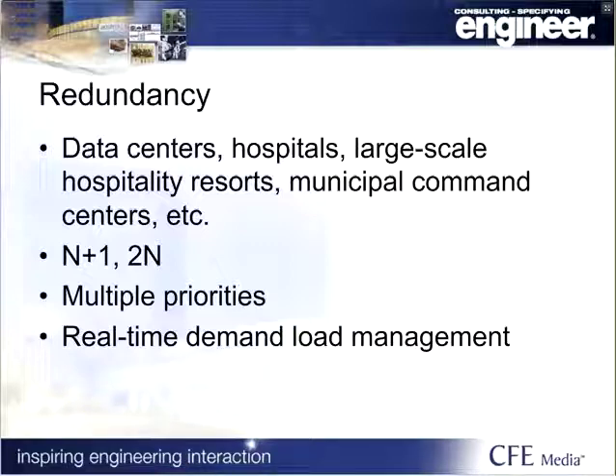Sometimes on very large projects where the generation capacity is quite large, you may have the opportunity to provide some degree of redundancy by breaking down the optional standby into multiple priorities. Sophisticated paralleling switchgear can provide real-time demand load management. The PSG would be programmed to ensure the EPS is available to the highest priority loads, emergency, and legally required standby, and optional standby loads considered critical to the client. The EPS would be sized for these based on connected loads. Additional capacity found during operation due to the actual load demand may allow a fourth priority to pick up less critical optional standby loads, but shed them during peak loads for the first three priorities.